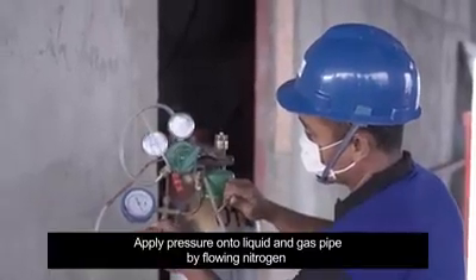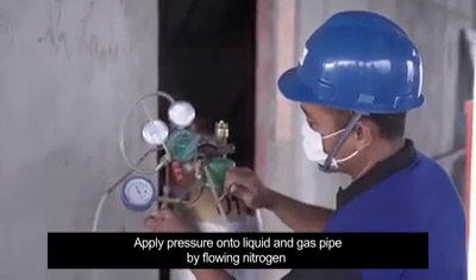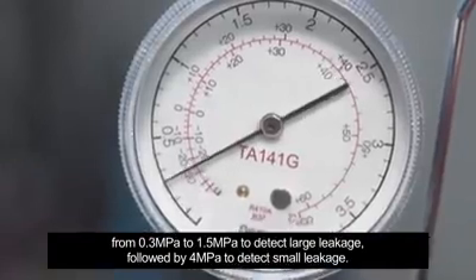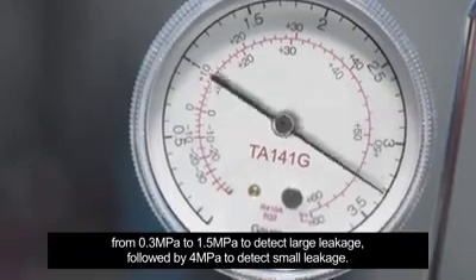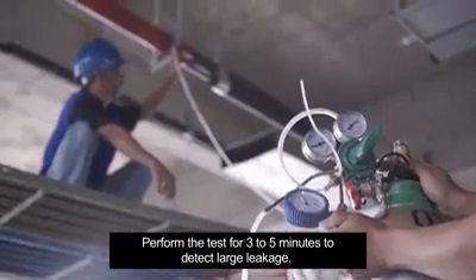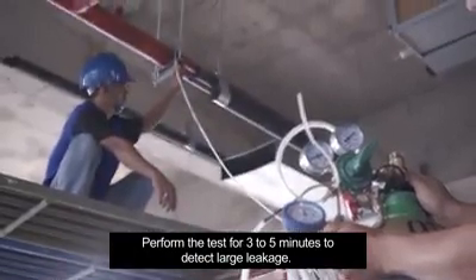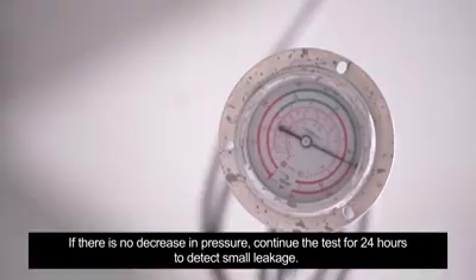Apply pressure onto liquid and gas pipe by flowing nitrogen from 0.3 megapascal to 1.5 megapascal to detect large leakage, followed by 4 megapascal to detect small leakage. Perform the test for 3 to 5 minutes to detect large leakage. If there is no decrease in pressure, continue the test for 24 hours to detect small leakage.